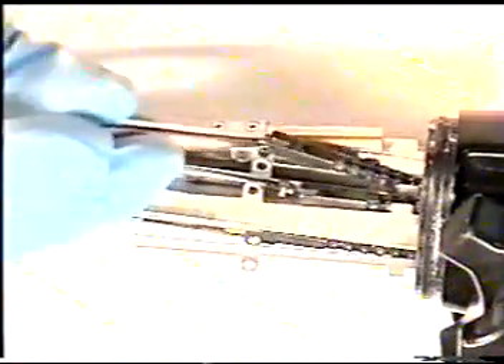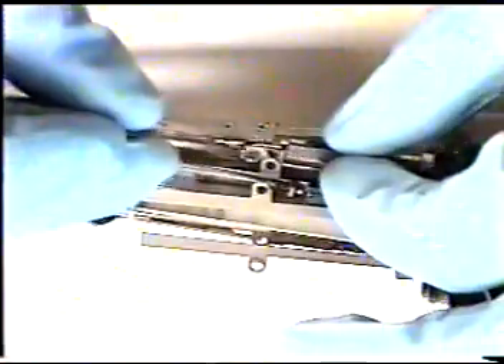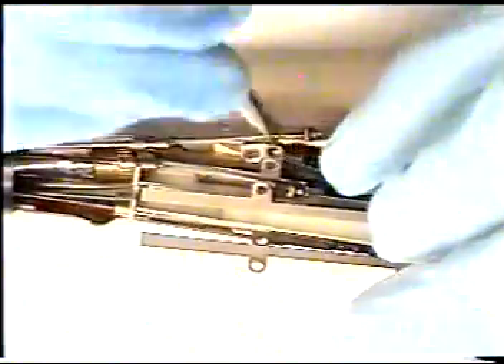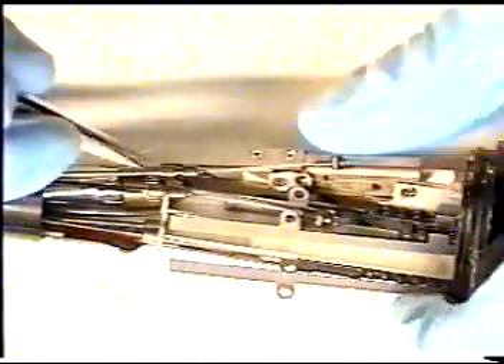We'll carefully remove the angulation control cables from the chain guides by sliding the chain guides up and over the control stoppers. Do this for each up, down, and left-right cable. Always be aware of the light bundles and image bundles as you're working on the endoscope. Please be sure to keep each specific cable in its holder.